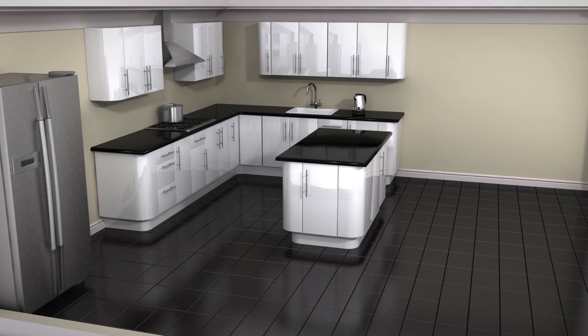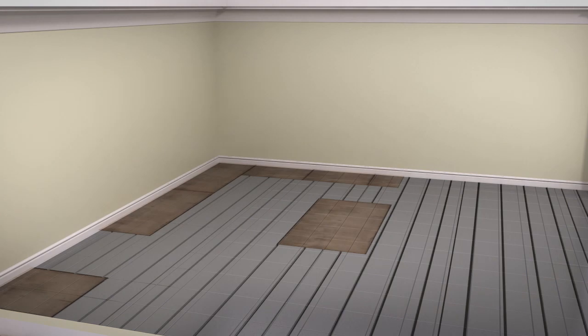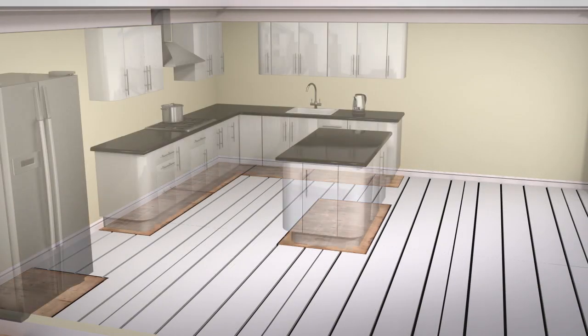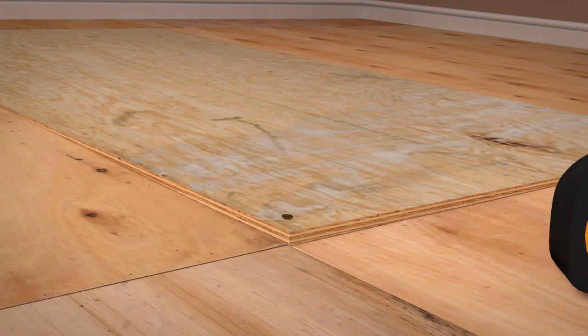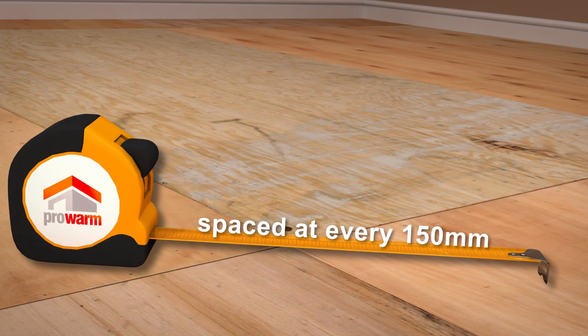For areas that do not require the underfloor heating, such as beneath kitchen units, an 18mm WBP plywood can be installed as a direct replacement. This will need to be secured to the subfloor using screws spaced at every 150mm centres.